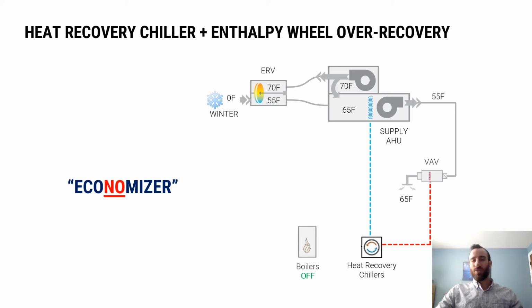Instead, what we're going to do is use the enthalpy wheel to pre-treat the outside air coming to the system, and then we end up with mixed air that's too warm. We're actually going to cool it mechanically with the cooling coil, and then run that through a heat recovery chiller, and that heat in the air handler becomes the heat we can then use in the building. So the heat pump in this case is a really strong example of using a heat pump to move heat to where we need it in a building instead of just creating heat anew.